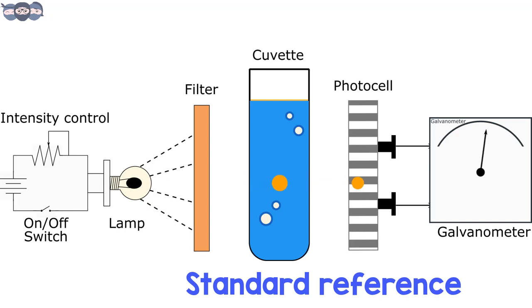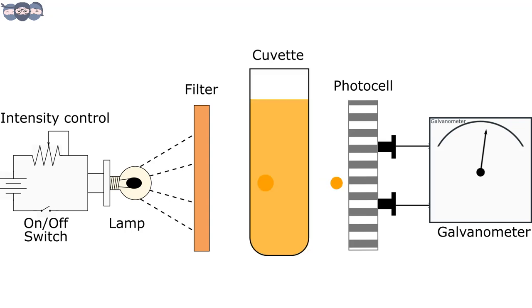Here, a part of light is absorbed and remaining part is transmitted. This transmitted light falls on the detector which produces photocurrent proportional to the light intensity. This photocurrent enters the galvanometer where readings are displayed. The instrument is operated in the following steps.